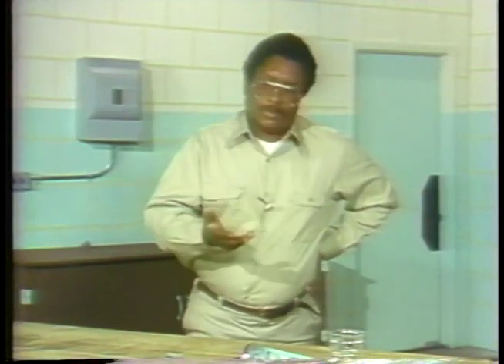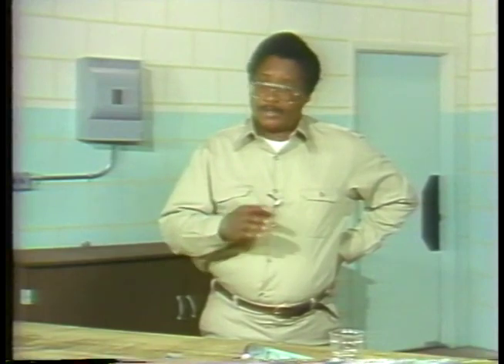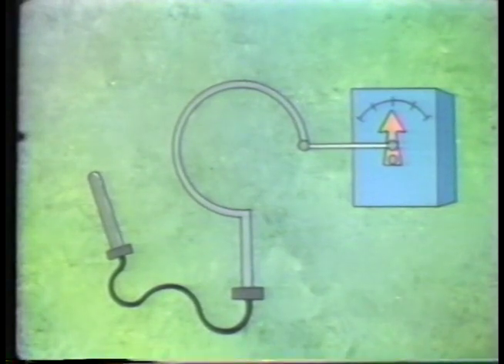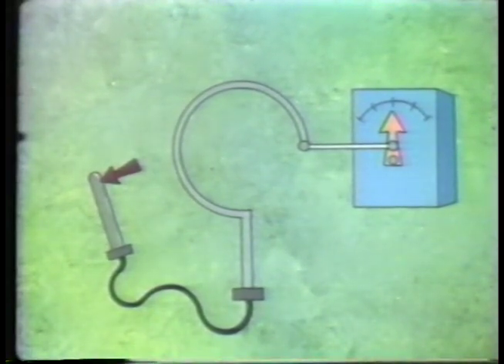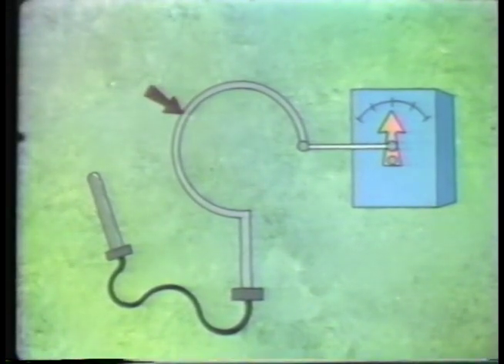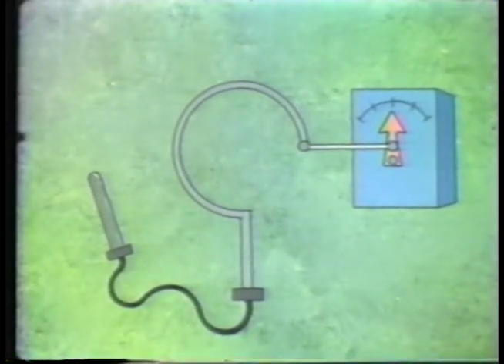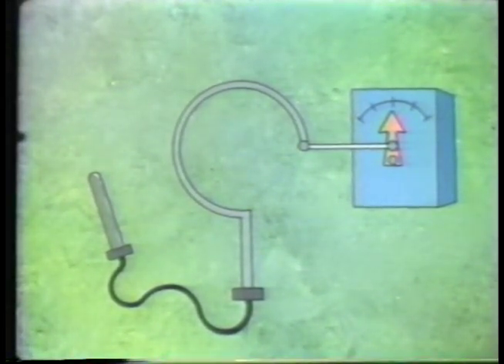While both liquid-filled and bimetallic thermometers are very useful and accurate, there are other methods you should be aware of. One common alternative is a filled thermal system. A typical filled thermal system consists of a sensing element, capillary tubing, a pressure measuring device (in this case a Bourdon tube), a scale, and a pointer. The sensing bulb, the capillary tube, and the Bourdon tube are all filled with a fluid such as alcohol or a gas. Filled thermal systems work on the principle that any change in temperature will cause a corresponding change in the pressure exerted by the fluid.